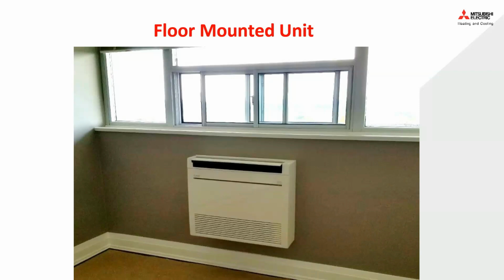Someone was asking which thermostat, and I think it's not necessarily the thermostat, but the controls. I'm assuming that they are Mitsubishi controls that are specific to the product you're using this with, right? No, it's a third party aftermarket controller. This is the direction that the smart controllers are going towards. There's one that's actually available on the market right now, made by BKR, and the dual fuel control with that thermostat was studied by Natural Resources Canada. They did a pilot study and a program on dual fuel switching. Also, Enbridge in Ontario ran a pilot using this technology to switch between air source heat pump and fossil fuel heating. We have other utility programs that are interested in doing similar studies.